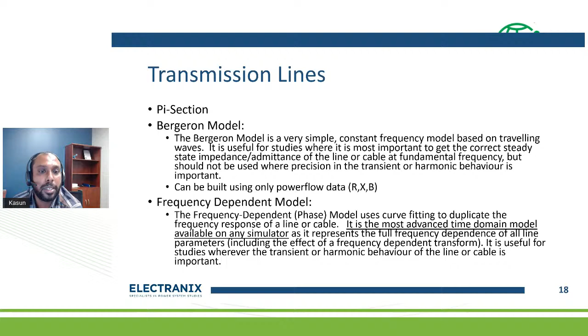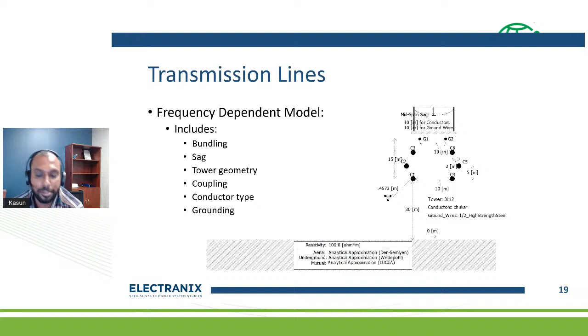This is how it looks inside when you go to the transmission line model, the detailed frequency dependent model. You can give all this information — the transmission line lengths, heights, distance between phase conductors, electrical data of conductors — and then solve it. All this information goes to the line constant program, which calculates RXB at each frequency, and that's used to curve fit to get the EMT model of the transmission line.